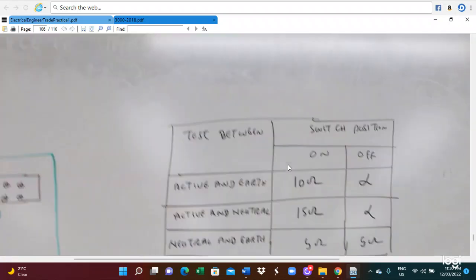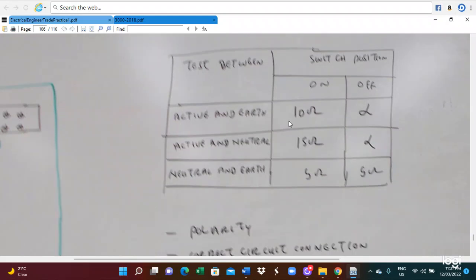Every two sides must be checked: switch on is 10 ohms, switch off is infinity. Active to neutral, switch on is 15 ohms, or infinity. Neutral to earth, switch on is 5 ohms, switch off is 5 ohms.